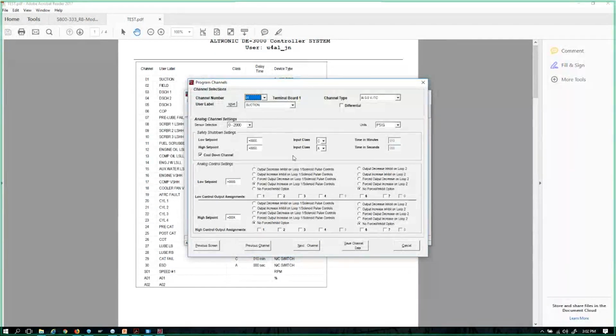Oh yeah, no doubt. And I mean, if somebody comes in and changes the high shutdowns to a class B, then you got problems. But that's why I spend quite a bit of time on this one. So just make sure your high pressures are always set as class A's and you're covered. Yes, sir. And then again, make sure your key critical channels, such as compressor oil pressure or engine oil pressure, are never selected. Even though it's a B timer, it won't be part of that cool down feature if you don't select it here. Yes, sir. Okay.